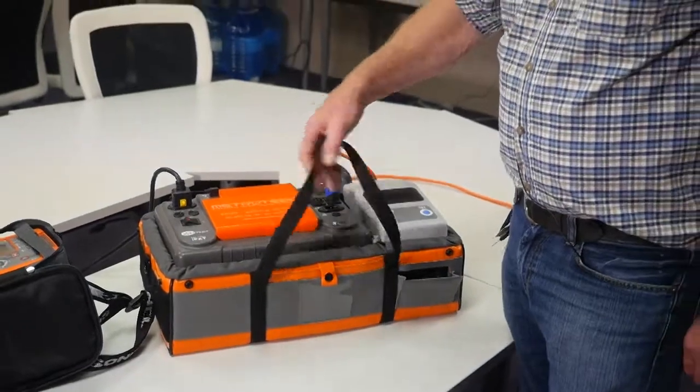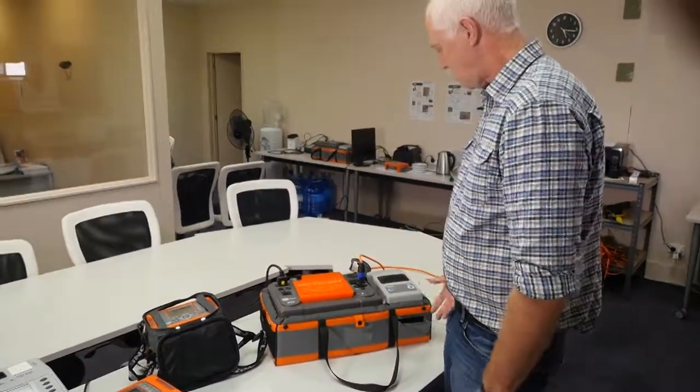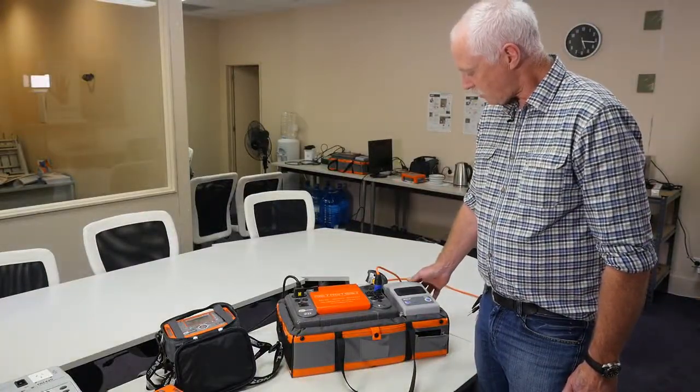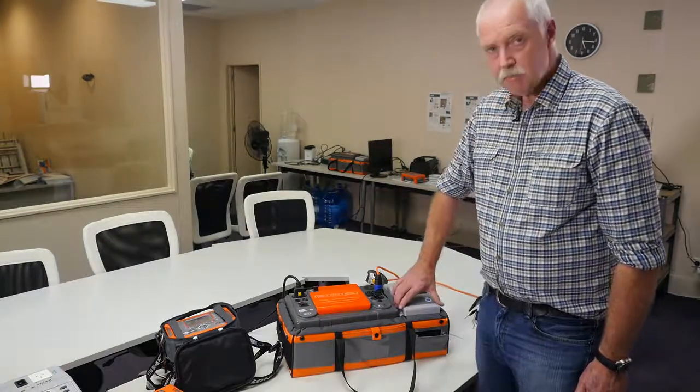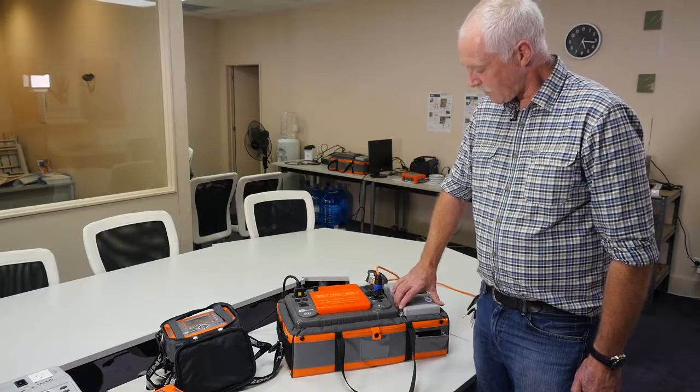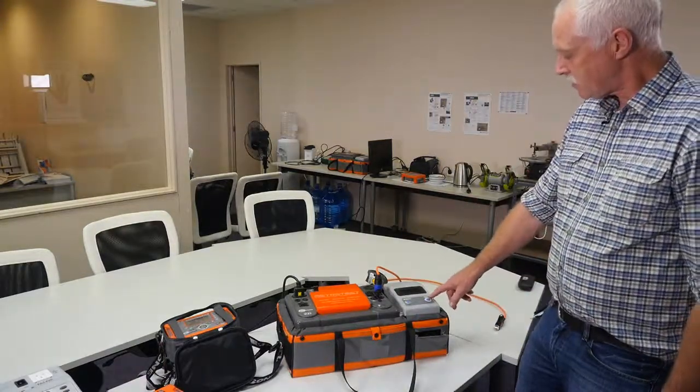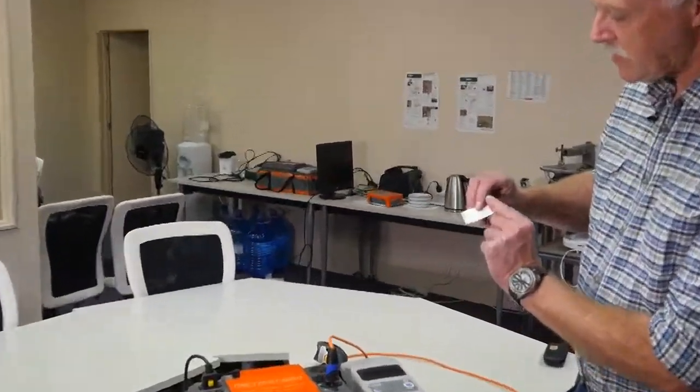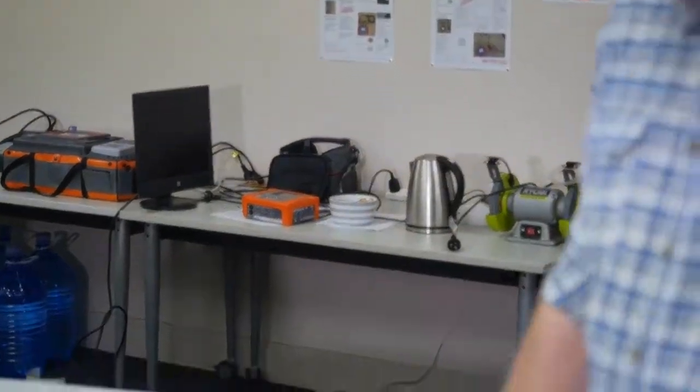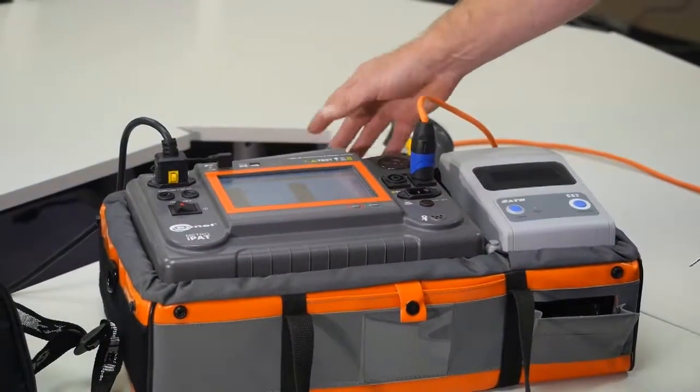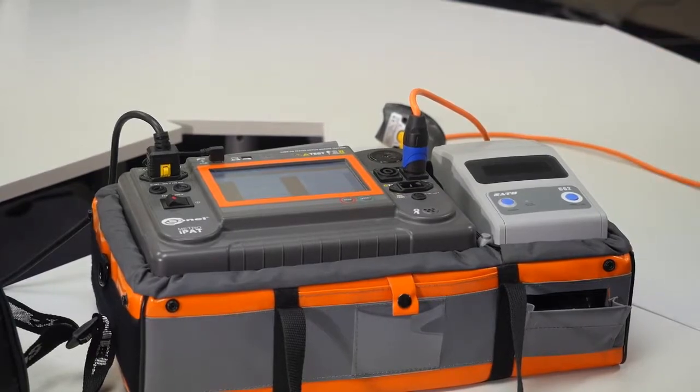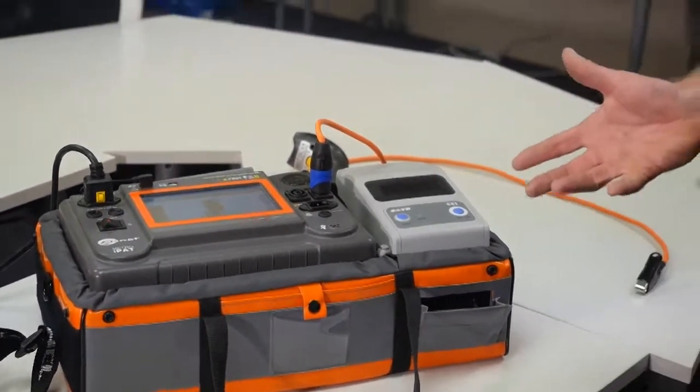It's not particularly, it's not a really light tester, but it's certainly not heavy. We have a girl working for us, who's a small girl, and she is quite happily carrying one of these around all day. So it's certainly not oversized. It has a thermal transfer printer built into it. So it's ideal. It won't fade or anything in the sunlight or heat. And what it can also do is it can print out a tag that has two different colors on it. So you can use a green tag or a red tag. And if you're doing a lot of testing, it also will be able to do double tagging, which means that, say if you're testing a computer, monitor and a lead, you can actually test them together and get two tags, which means that you've basically cut your testing time in some situations in half.